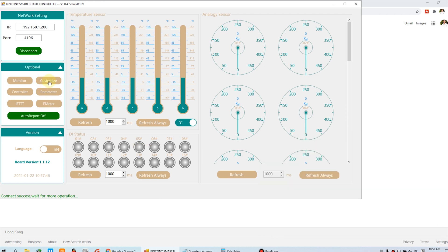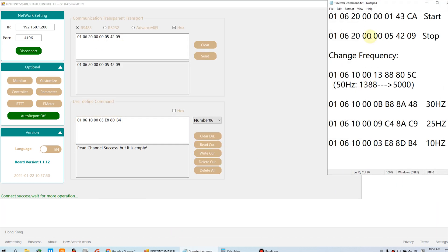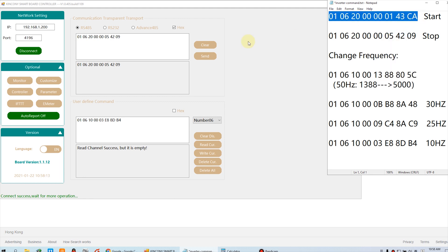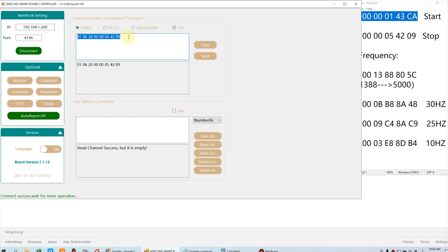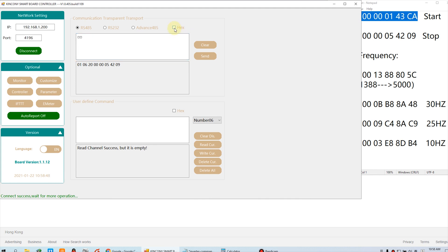Now we begin to create our custom function for the command. I have saved this command for start, stop, and change the frequency — like frequency 1, 2, 3, 4. These four kinds of frequencies for six buttons. So we can copy this start command. We delete the previous content. Then we paste. Now this is the start command by RS485. As a protocol, you need to check hex mode, because I have used the hex protocol command. If you send ASCII string, you don't need to check. If you need to send hex format, you need to check this and paste the command.